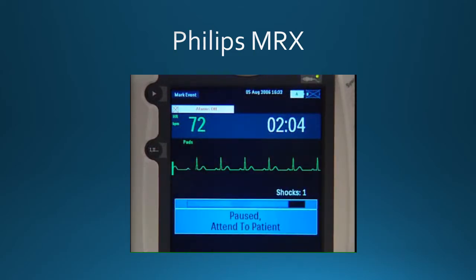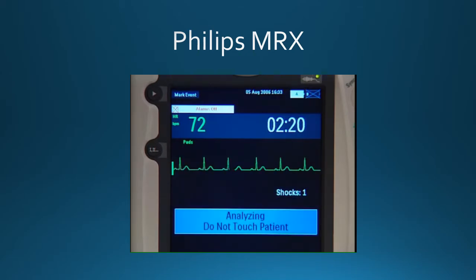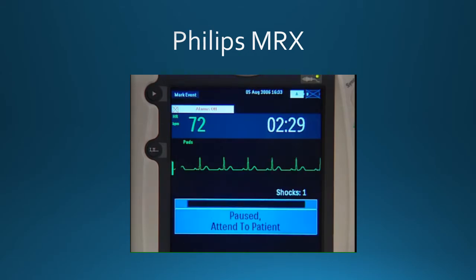After a shock is delivered, the device pauses and you are prompted to begin CPR if needed. Paused. If needed, begin CPR. The MRX reanalyzes the ECG when the pause period ends or you press Resume Analyzing. Analyzing heart rhythm. Do not touch the patient. If a shockable rhythm is not detected, the device tells you No shock advised. The MRX supports the American Heart Association's and European Resuscitation Council's 2005 resuscitation recommendation of immediate CPR after a no-shock advised decision, or after one shock is delivered.